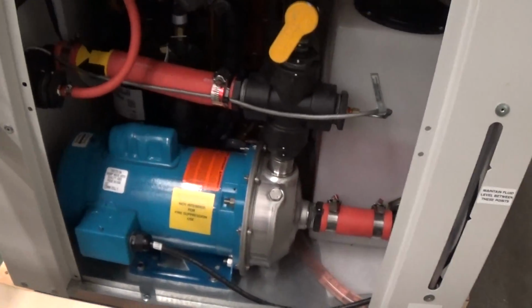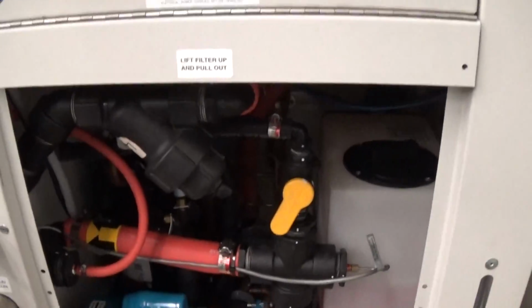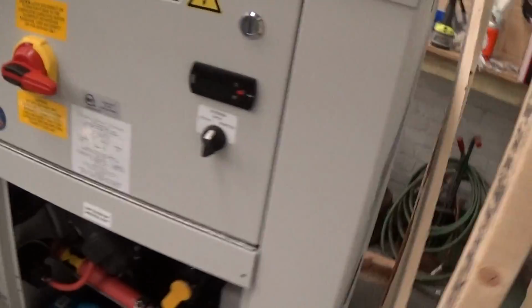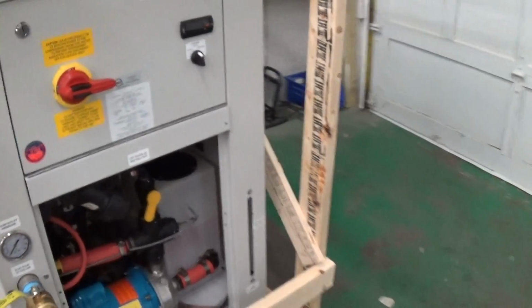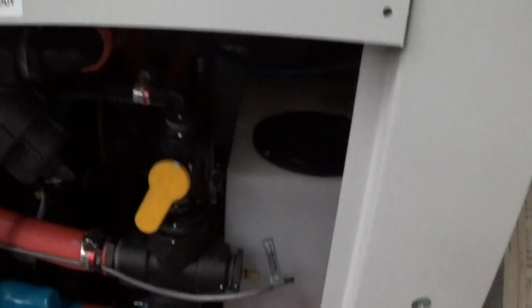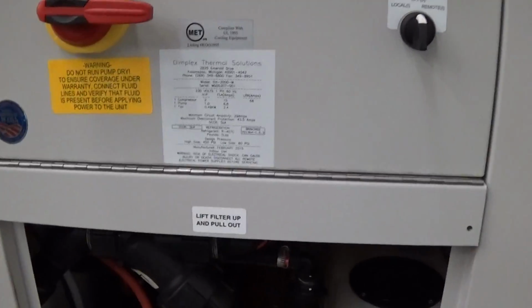Before we put power to the unit, I'll show you this side cover that I took off here. This air filter can remain off while we run the unit. These side covers here, which seal in the area for the condenser, need to stay in place, because this style has a condenser that sits flat up above here, kind of like a sealed chamber.